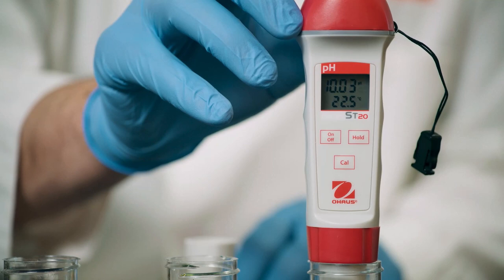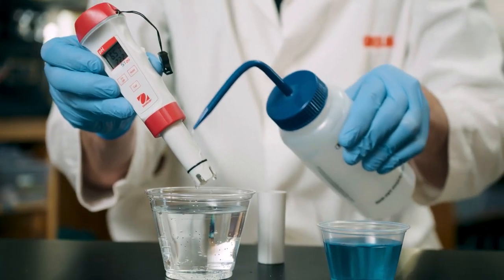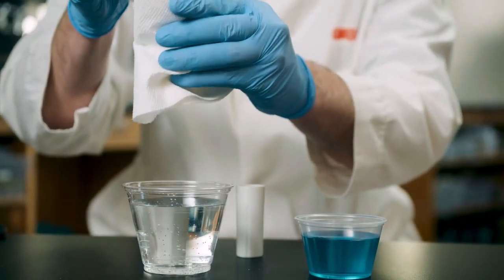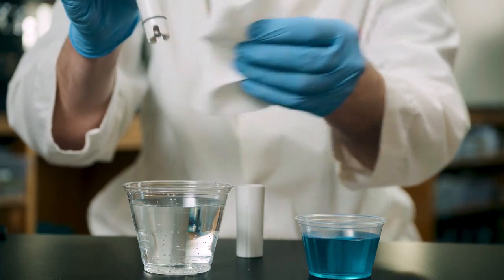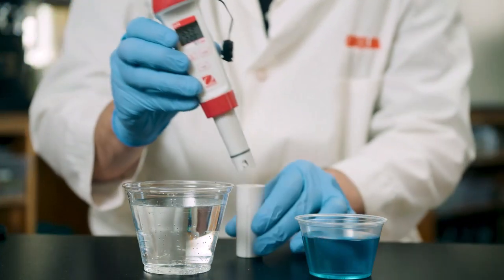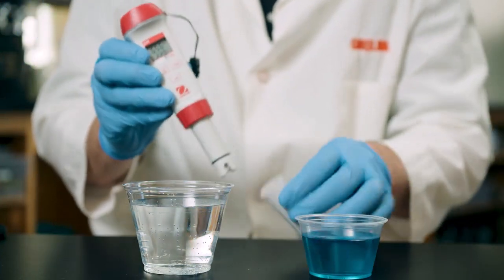Note, again, in this case, because the temperature was 22.5 degrees Celsius, the pH of the buffer is 10.03. Due to auto temperature compensation, the pH display shows 10.03. Rinse off the pen meter one final time with distilled water and wipe clean. The pen meter is now calibrated and ready for use. If you are not going to immediately use your pen meter, replace the cap.